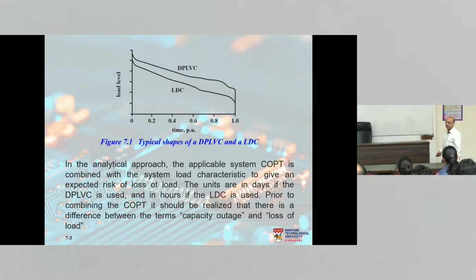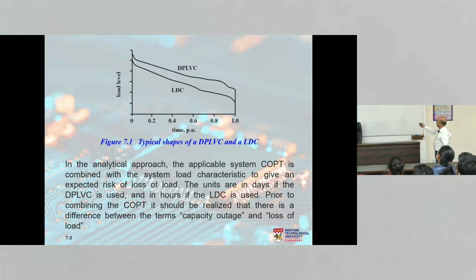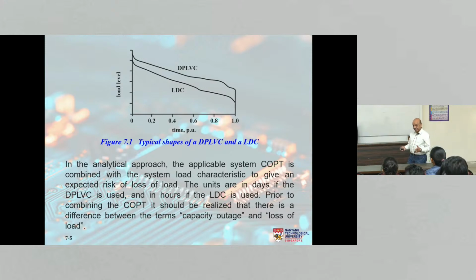So the typical shapes of these two curves are shown here: the daily peak load variation curve and the load duration curve, and this is the time in per unit. It could be over a month, over 6 months, or over 1 year. If it is 1 year, then this represents 8,760 hours or 365 days. So for the daily peak load variation curve, it could be 365 days, yeah? Or for the load duration curve, if you are doing it for the whole year, it could be 8,760 hours. If you are doing it for a month, it is 720 hours, okay? 24 times 30. So in the analytical approach, we use the COPT and we combine it with the load characteristic to get the risk. Yeah, as simple as that.